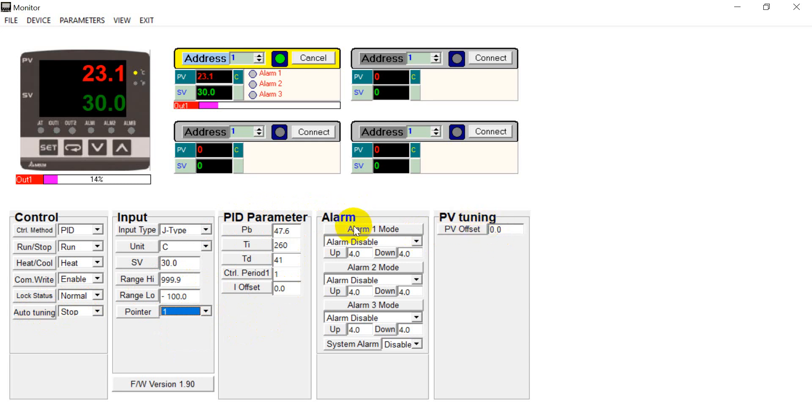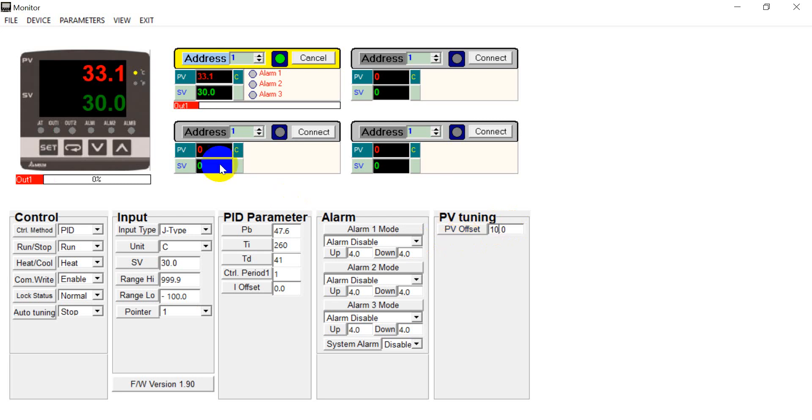Then here you can use the software to set the alarm. Besides, you can also put some offset. So for example, if now we put the 10 over here. So you will see the maximum value will increase 10. So this is the offset function.